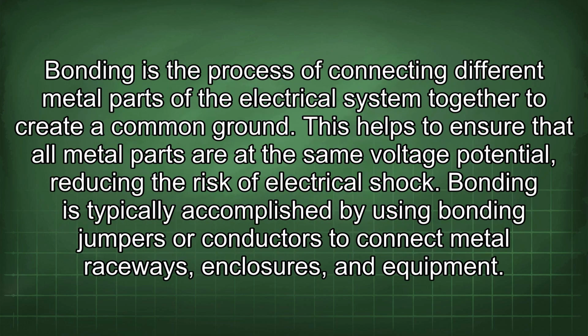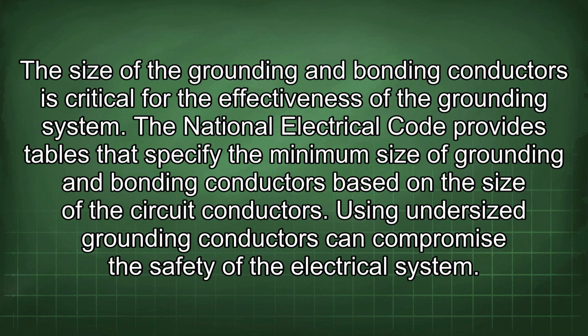Bonding is the process of connecting different metal parts of the electrical system together to create a common ground. This helps to ensure that all metal parts are at the same voltage potential, reducing the risk of electrical shock. Bonding is typically accomplished by using bonding jumpers or conductors to connect metal raceways, enclosures, and equipment. The size of the grounding and bonding conductors is critical for the effectiveness of the grounding system.